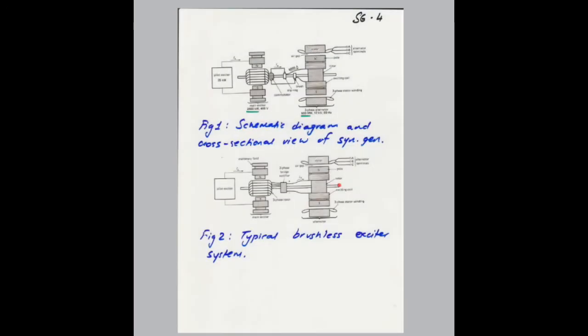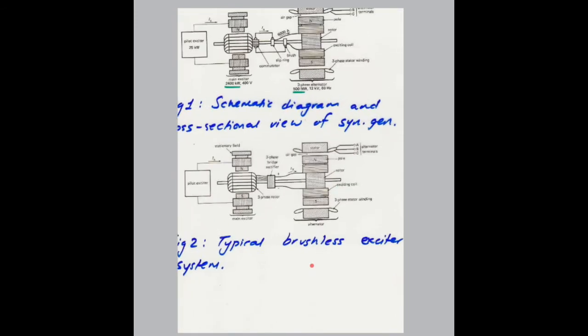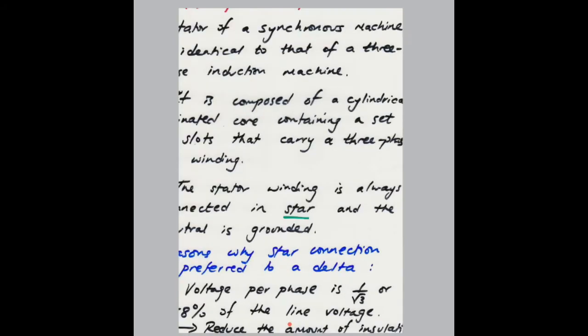So if we go back to figure 2, so if you look at figure 2, this is employing a brushless exciter. So instead of having the commutator, slip ring, and brush system to convert the AC current to DC, now we've basically used a 3-phase bridge rectifier to convert the AC current to DC current, which is required for your rotor circuit, right? So we're using a power electronic rectifier to convert this current, and now we no longer need this inefficient system, and this is more efficient and obviously less maintenance cost on your generator.